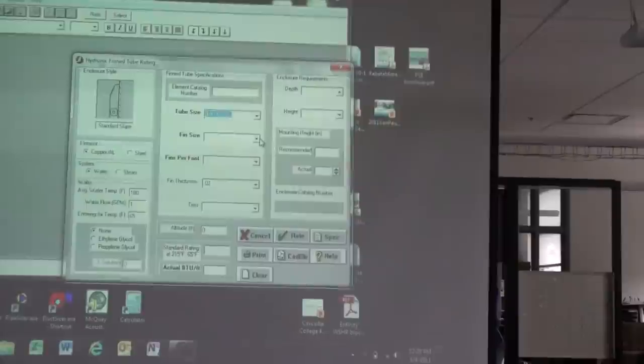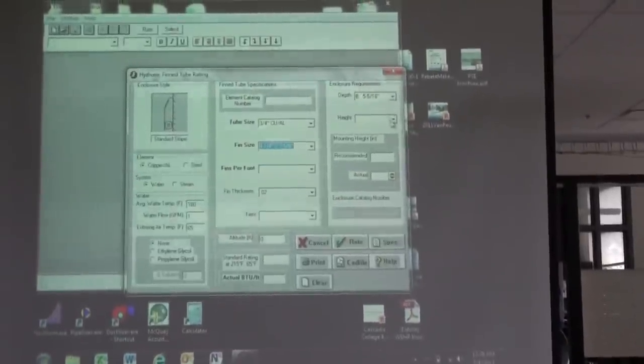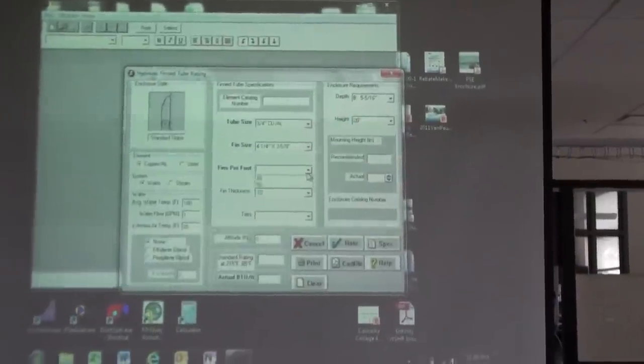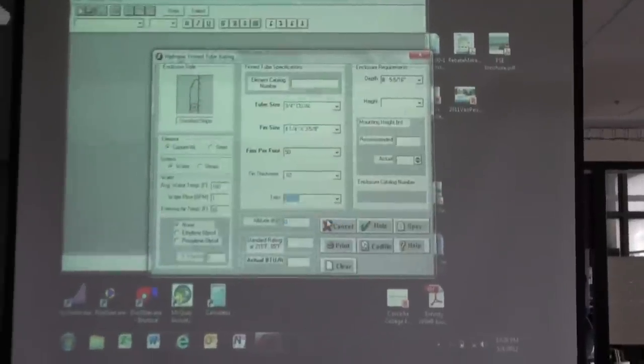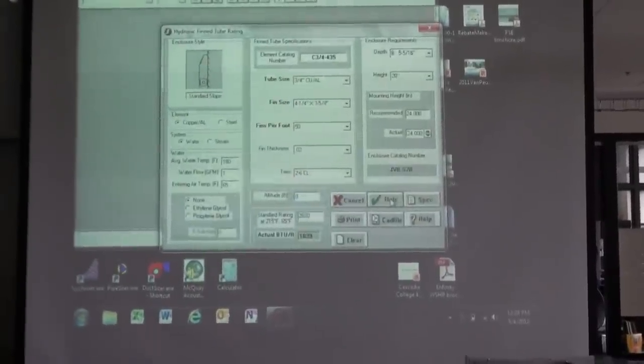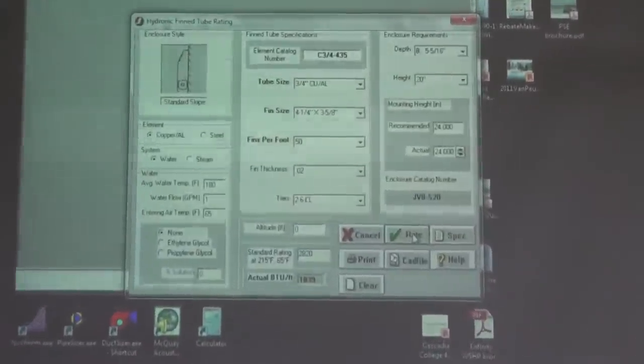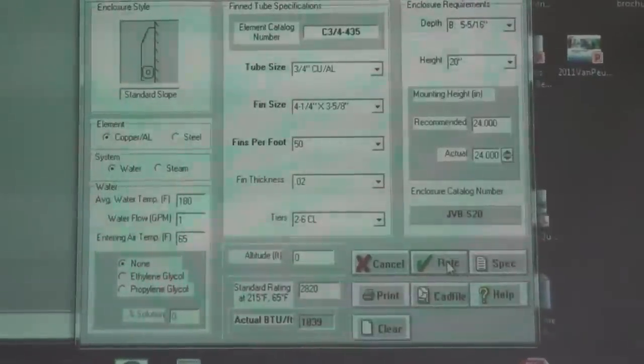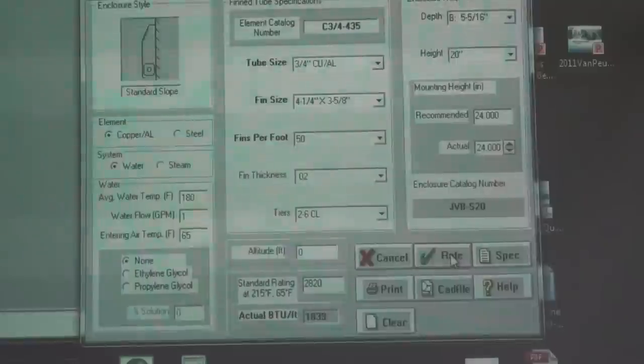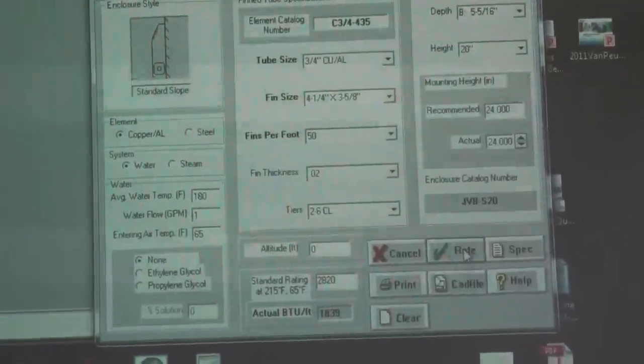I'll just use a three-quarter inch tube. One inch tubes are too big to get as much heat transfer. Use a fairly large element with maximum fin count, throw in those two tiers, I'll rate it. Just over 1800, 1800 BTUH per linear foot.